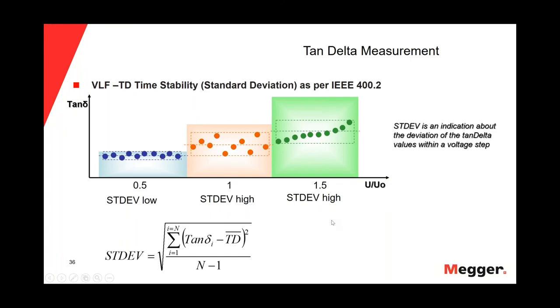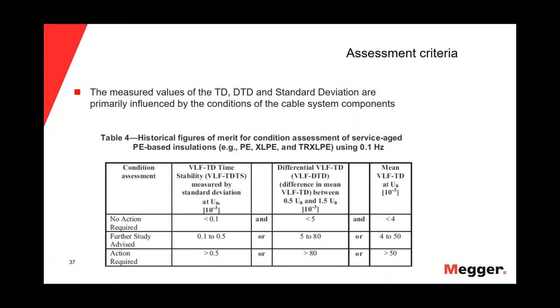Once we have evaluated these three criteria, we can use the tables in IEEE 400.2 to compare our results and see what the condition assessment of our cable is. We can have different condition assessments depending on the values of the VLF time stability, the delta of the tan delta, and the mean value of the tan delta. The possible assessments are: no action required, further study advised, and action required.